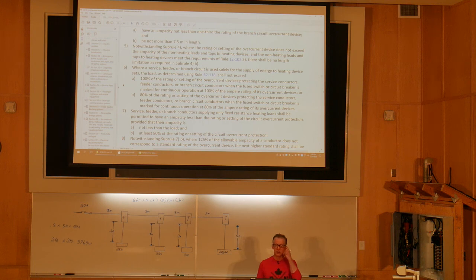You're not going to get 100% rated circuit breakers in a residential occupancy. So really you're down at 6B. Where a branch, so this is a branch circuit in this case. So where a branch circuit is used solely for the supply of energy to heating device sets, the load as determined using 62118 shall not exceed 80% of the rating of the overcurrent devices protecting the service conductors, feeders, or branch circuit conductors when the fuse switch or circuit breaker is marked for continuous operation at 80% of the ampere rating of its overcurrent device.